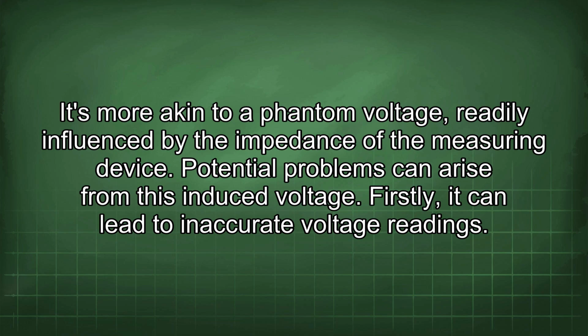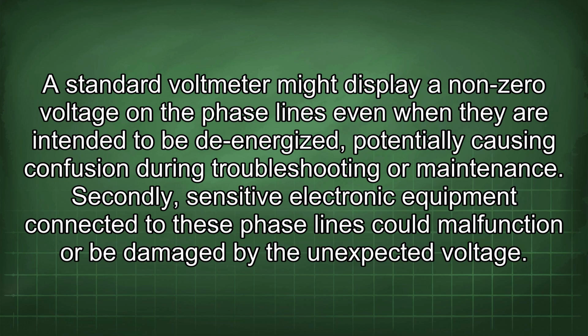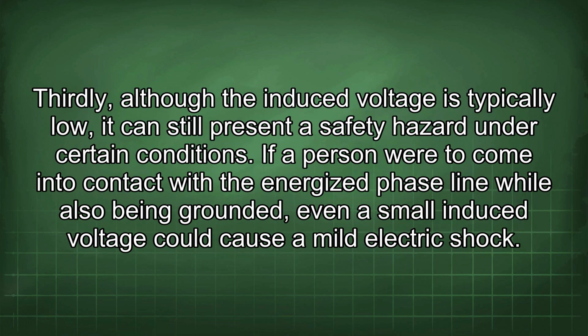Firstly, it can lead to inaccurate voltage readings. A standard voltmeter might display a non-zero voltage on the phase lines even when they are intended to be de-energized, potentially causing confusion during troubleshooting or maintenance. Secondly, sensitive electronic equipment connected to these phase lines could malfunction or be damaged by the unexpected voltage. Thirdly, although the induced voltage is typically low, it can still present a safety hazard under certain conditions.